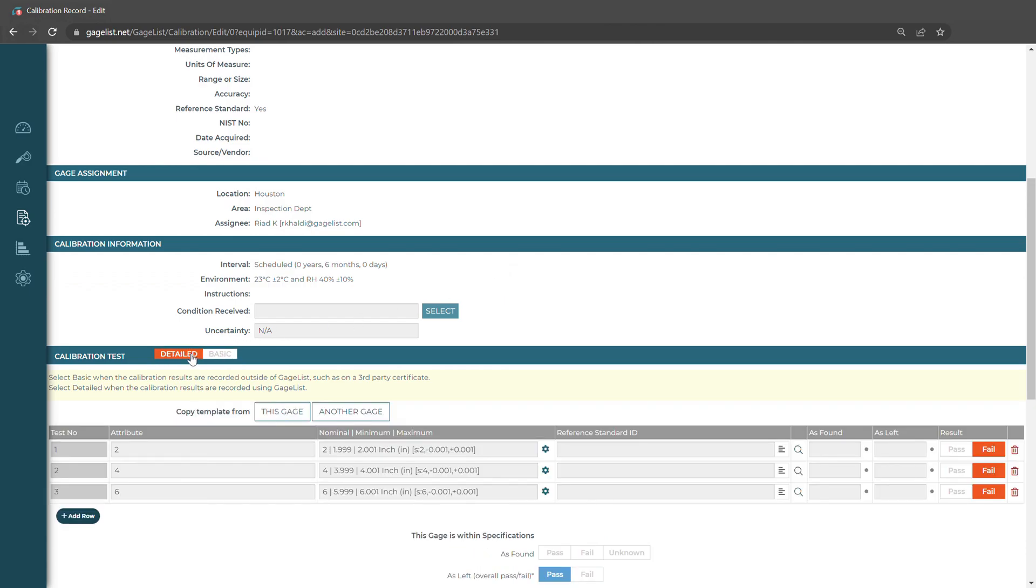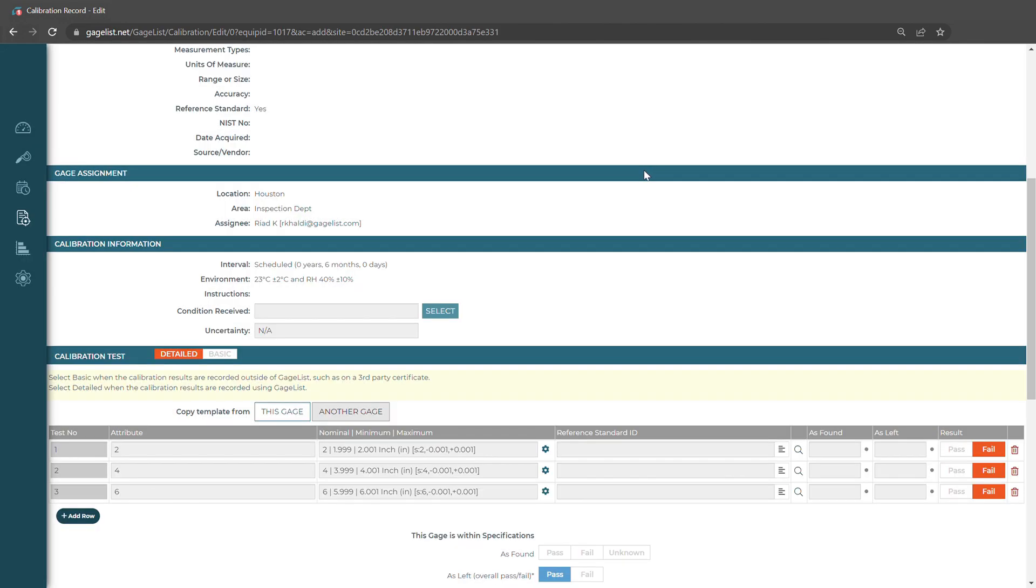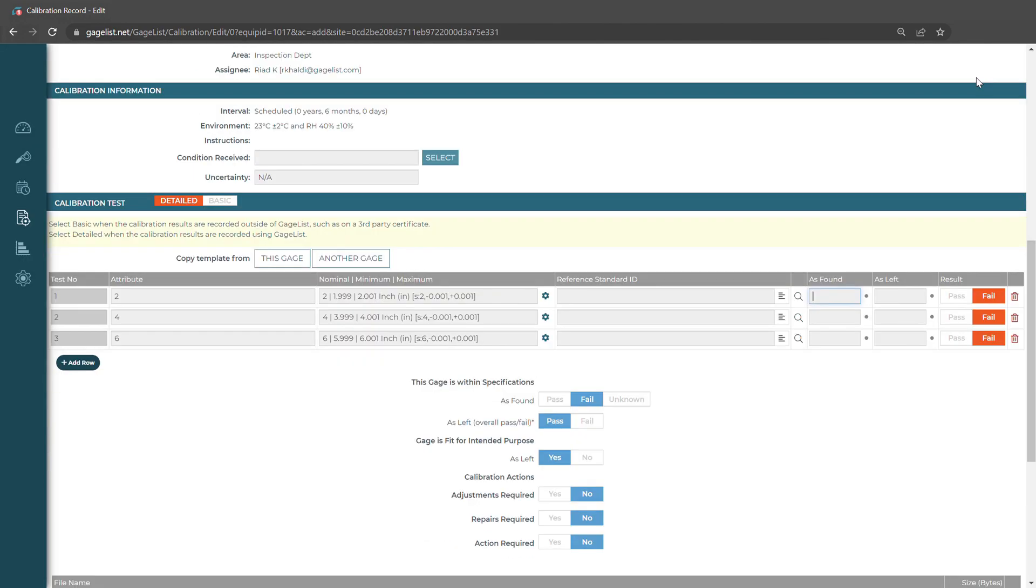If we have an internal test that we want to perform, we would select Detailed. It's automatically going to pull in our test template that we set up on the gauge record. If we want to copy it from another one, we can do that by selecting another gauge. Now with that setup, we can perform our internal calibration test.